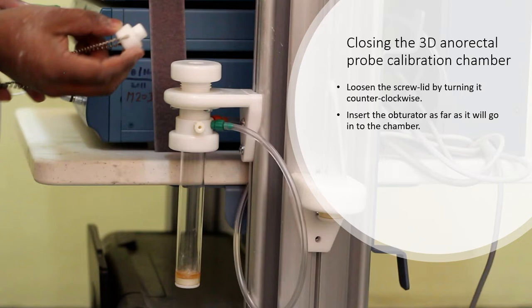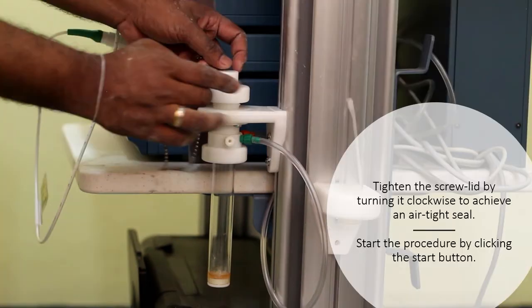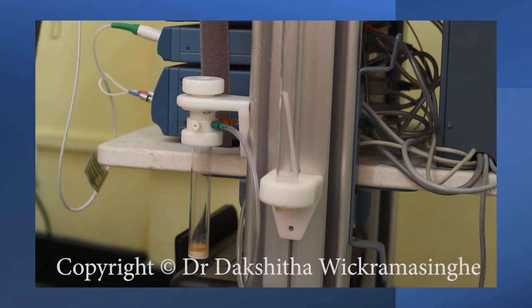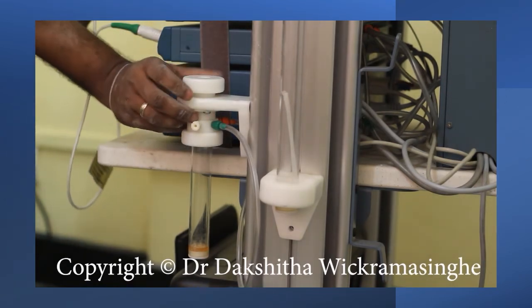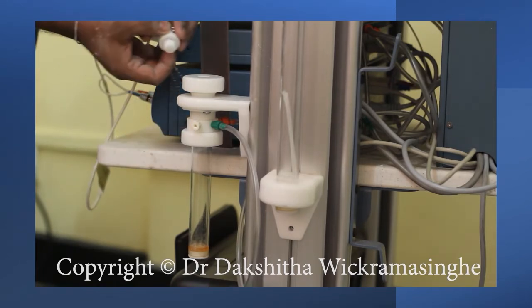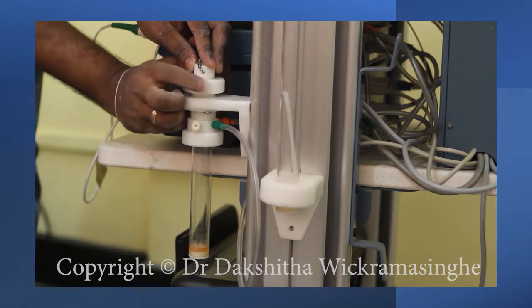Before calibrating the esophageal probe, the 3D anorectal calibration chamber must be closed. First, loosen the screw lid by turning it counterclockwise. Then, insert the obturator as far as it will go into the chamber. Then, tighten the screw lid by turning it clockwise to achieve an airtight seal. You can start the calibration procedure by clicking the Start button. Before using the 360-degree probe chamber for calibration, you must close the 3D probe chamber by using the obturator provided.